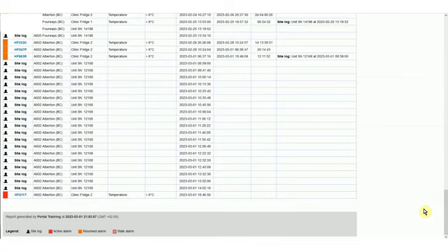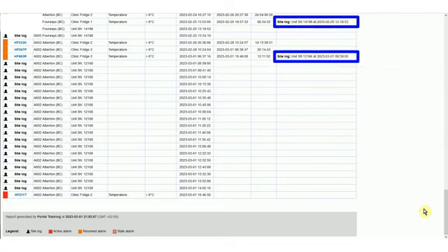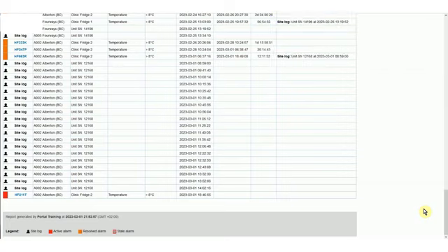In terms of alarm event icons, currently active alarms are marked with red icons. Alarms that were previously active but have been resolved by pushing a Cold Cloud device's alarm mute button are marked with an orange icon. As mentioned earlier, non-alarm alarm mute button pushes are shown as site log entries. If any alarm is marked with a stale alarm icon, that alarm is currently active and has been active for longer than the predefined stale alarm period.